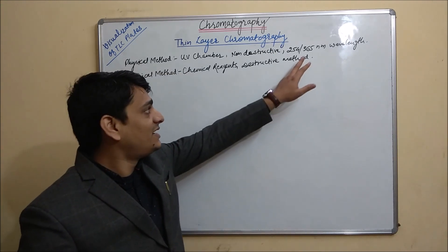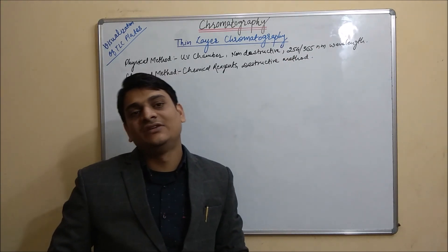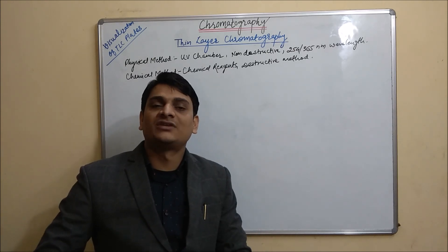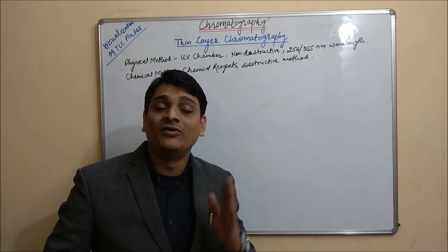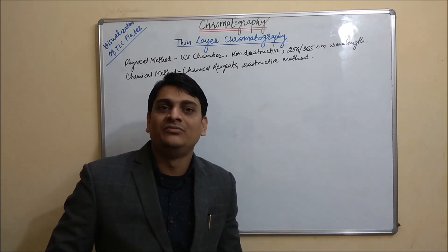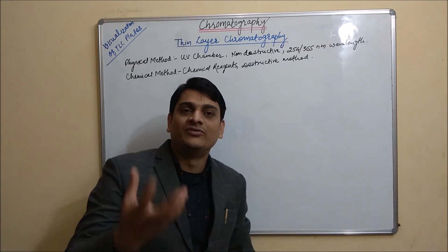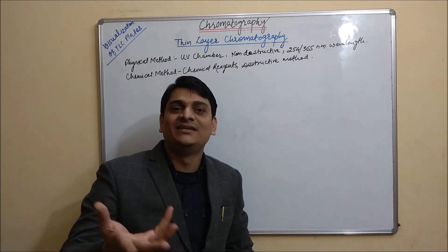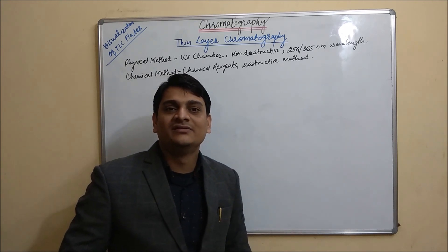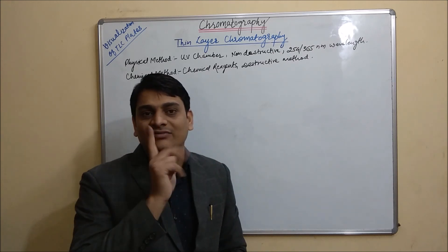The second wavelength is 365nm. Why we are using 365nm? Most of the fluorescent compounds give their fluorescence at 365nm because fluorescent compounds get activated and release their fluorescence at 365nm. That is why we are using two wavelengths — one is 254nm and second one is 365nm.